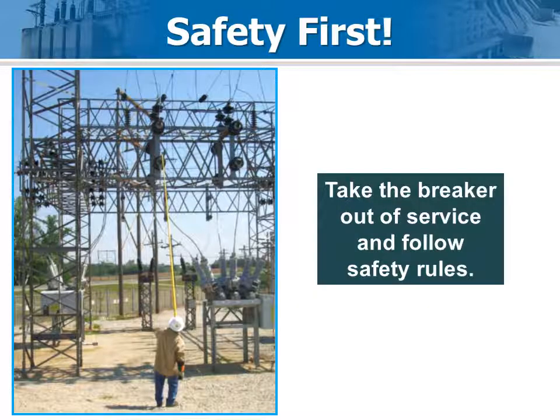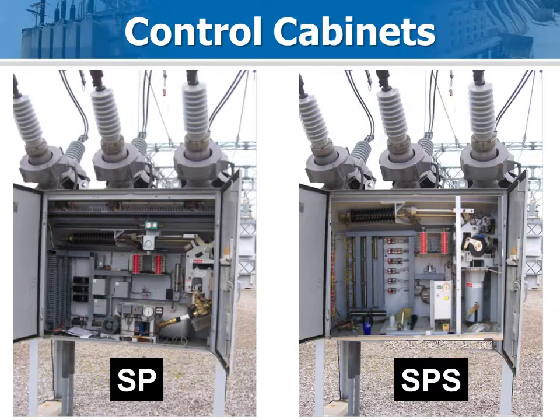Schedule the outage in advance so things go smoothly. If the crew shows up prepared with all the parts, installation generally takes less than 2 hours. The SP and SPS have similar control cabinets, and there is usually plenty of extra room to install the Optimizer 2 main unit. The left-hand side of the cabinet is good because that is where the CT terminal blocks are, so routing the wires is much easier.